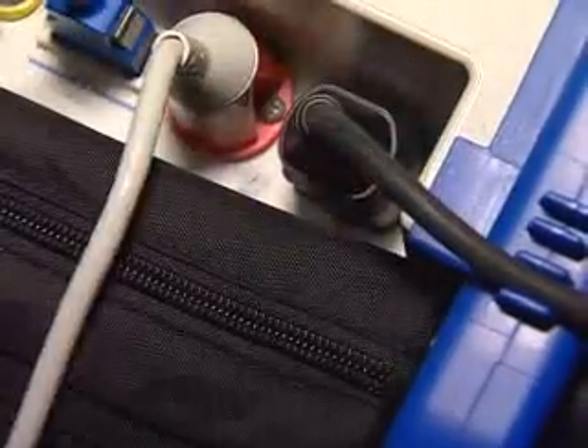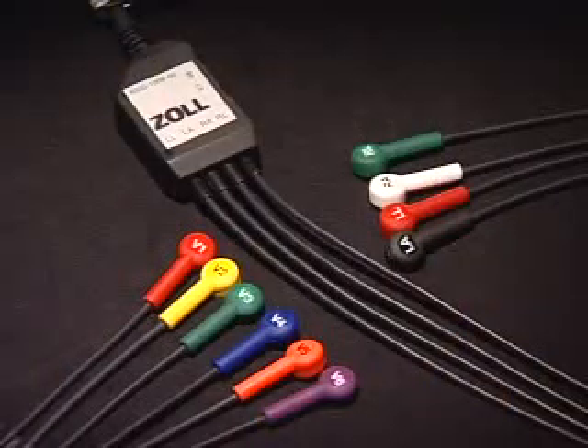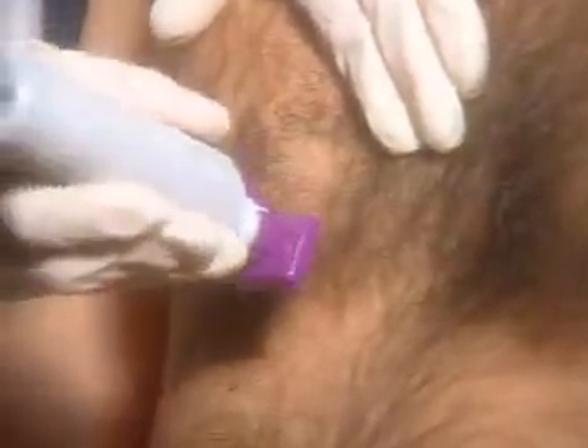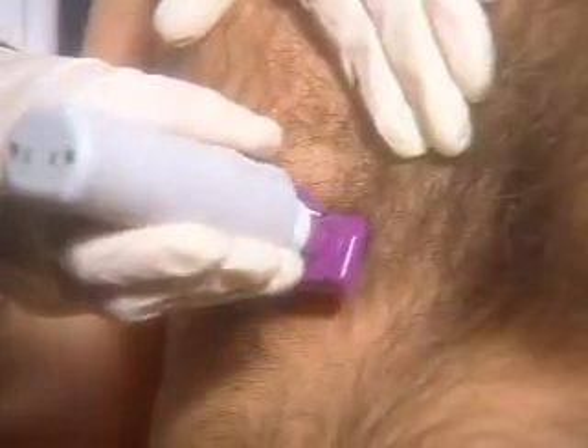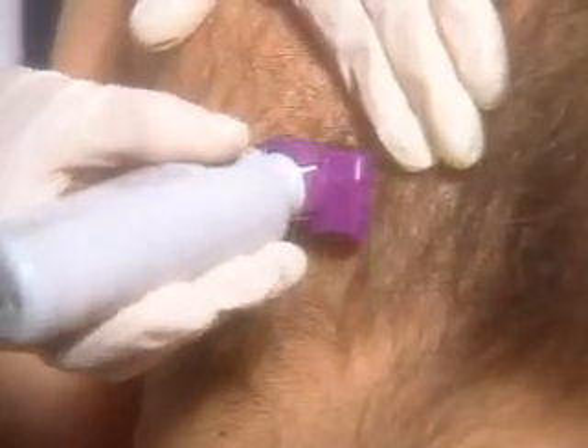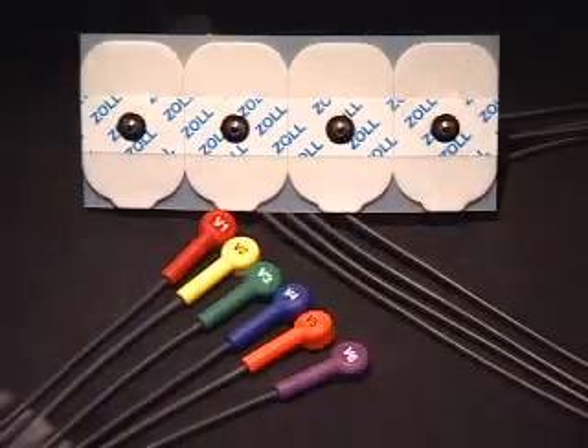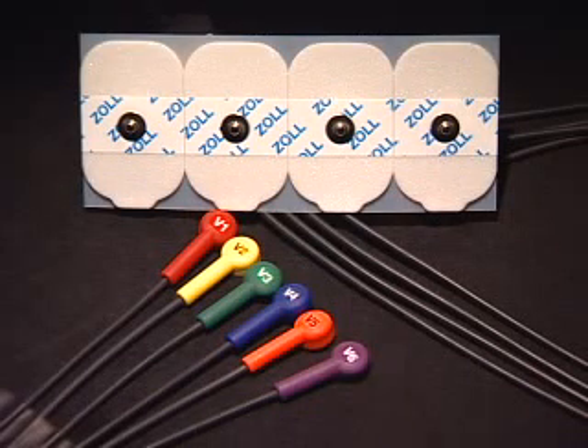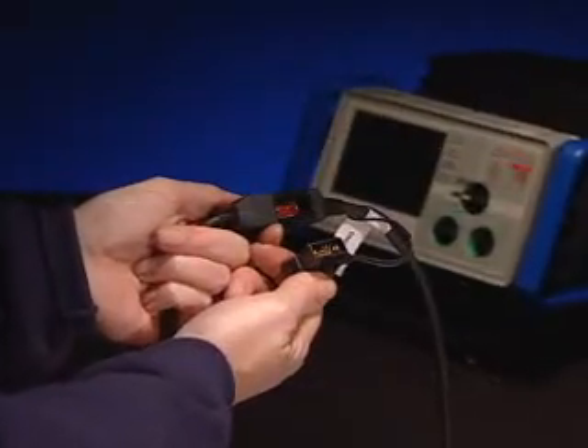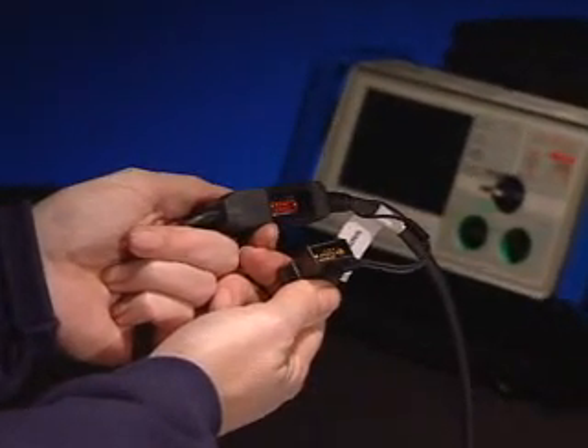The 12-lead ECG cable should be attached to the cable connector in the rear of the E-Series. This cable comprises the 4 limb leads and 6 chest leads. Care should be taken to properly prep your patient's skin. This should include clipping excessive hair and light abrasion of the skin to ensure proper electrode contact. High-quality silver chloride electrodes should be attached to the ECG cable snap connectors and should be placed on your patient's well-prepped skin.